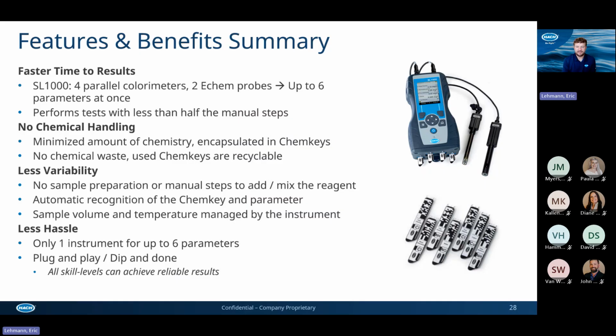It's going to perform the tests in less than half the time of manual steps, and in some cases we saw it cut down even further. No chemical handling. So again, we don't have reagents. We don't have to pipette samples, so we're not looking at sample volume. And then there's no chemical waste. So the ChemKeys can be recycled, but ultimately we don't have that chemical waste. No sample prep, no mixing, no swirling, no shaking, automatic parameter recognition. So we put any ChemKey into the instrument. It's going to automatically recognize what range we're looking at, what wavelength we're looking at, what parameter we're looking for. So all of that is automated and streamlined.